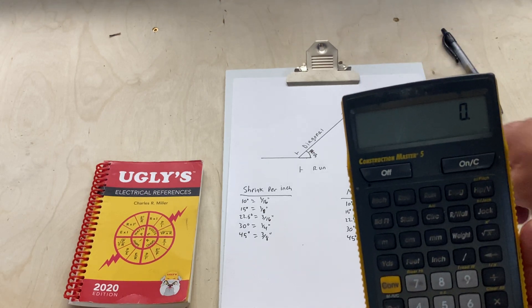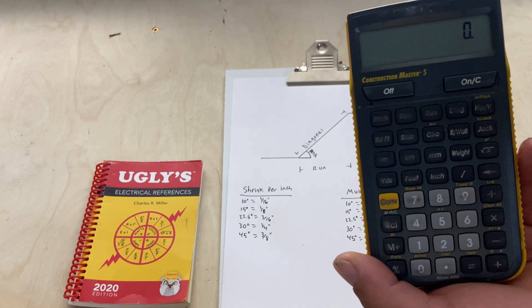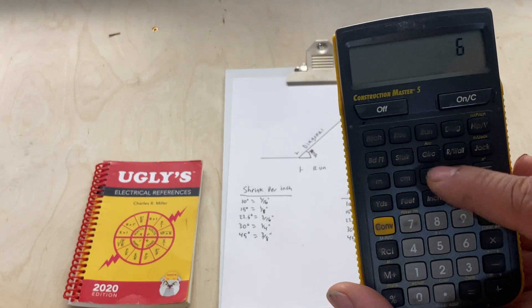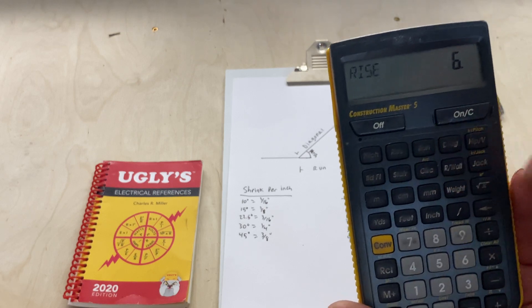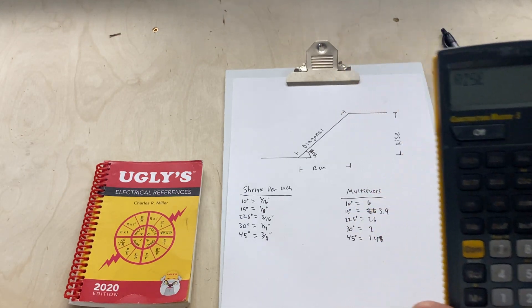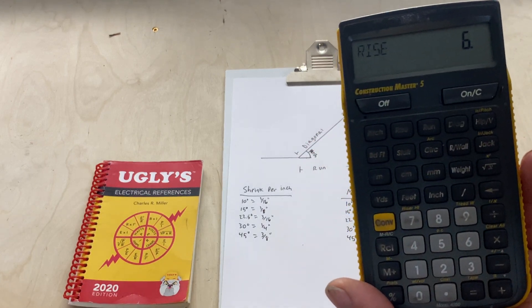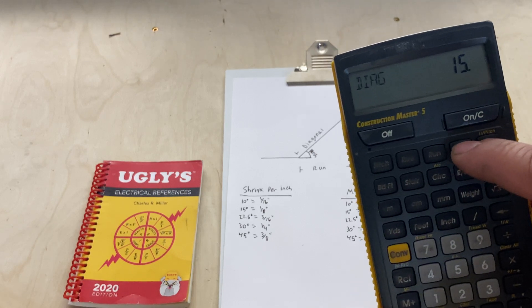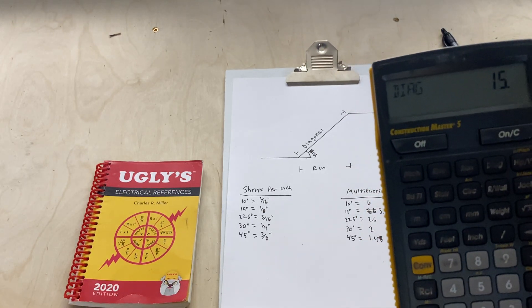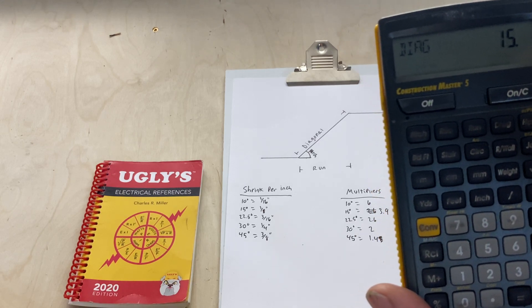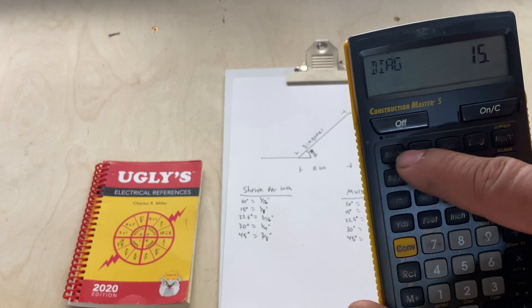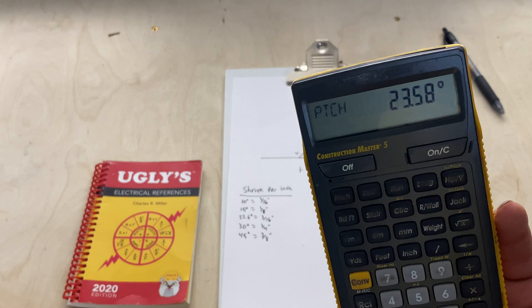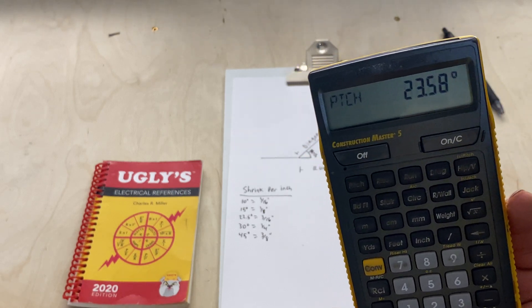Just for an example, let's say it's a six-inch rise, that's a six-inch offset that you measured. Let's say their center-to-center ends up being 15 inches. You'll put 15 diagonal because that's their center-to-center. Once you've entered those two, all you have to hit is pitch and it tells you it's about a 23 and a half degree bend.